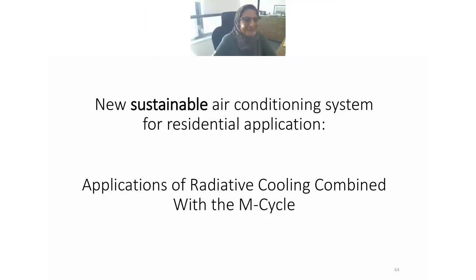Thank you, Dr. Chicron, for the presentation of the second application. We're going to move to something more complex, because in all our work we were trying to find if there is a passive way to have a space air conditioned without mechanical ventilation, even in a challenging hot climate such as that of Kuwait. The catch is that indirect evaporative cooling can be used because you have a dry climate and a low dew point, and this is why the combination of the radiative cooling panel and the M cycle is going to work. Let's see how that has been done.